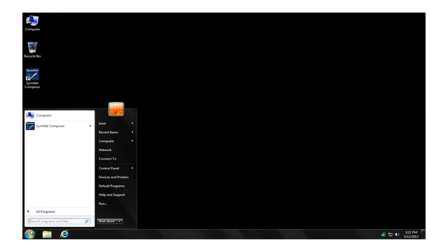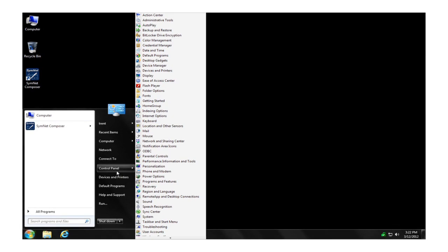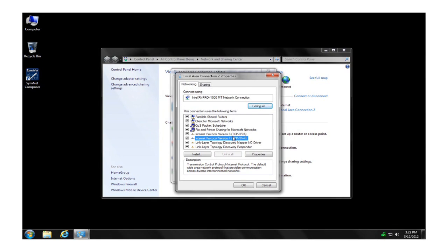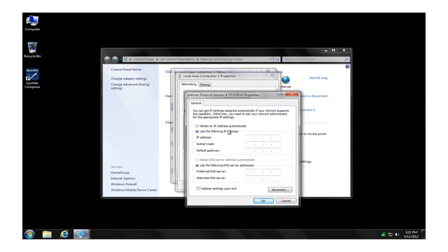When there is no DHCP server present to assign IP addresses to either Edge or your PC, you may need to configure your PC with a static IP in the range of 169.254.x.x, where .x.x is the last six numbers of your choice, and a subnet mask of 255.255.0.0 in order to communicate with Edge in a direct connect mode.